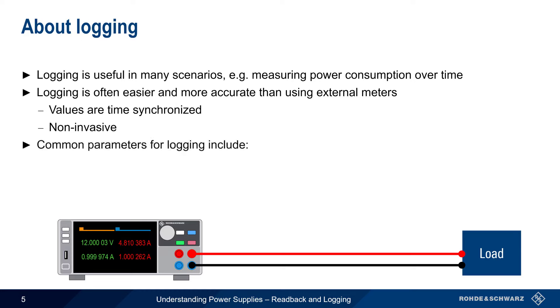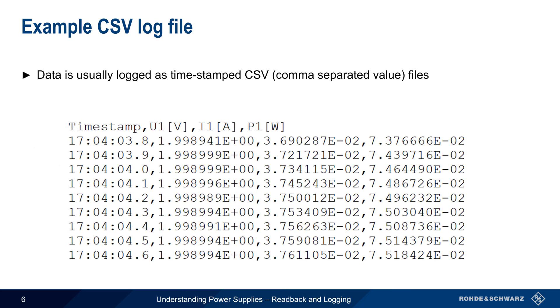When configuring logging on a power supply, parameters include the logging interval — or time between stored measurements — and the start/stop conditions, or duration for the logging. For example, logging may be started and stopped manually, or based on some user-defined time or event. Logged data is normally stored in plain text files as so-called comma-separated values, or CSV, for ease of processing.